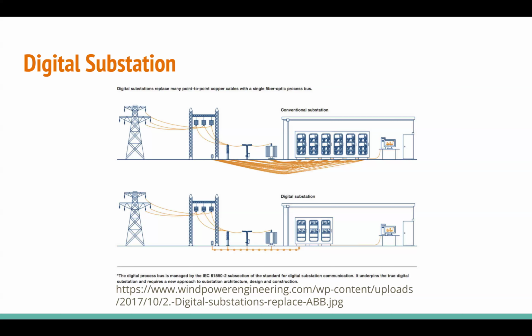The other issue has just been equipment availability and cost. Up until now, if you wanted a 61850 based relay for digital substations, it would generally be more expensive than the conventional equivalent, so that was also holding people back. I think that's basically evened out now—if you're buying a purely digital relay versus one that accepts hardwired inputs, you're probably going to come out pretty on par cost wise.